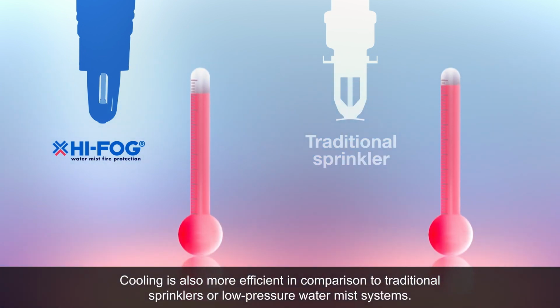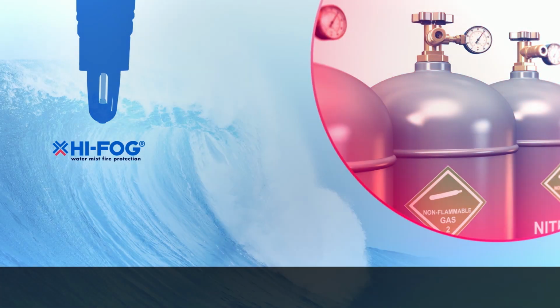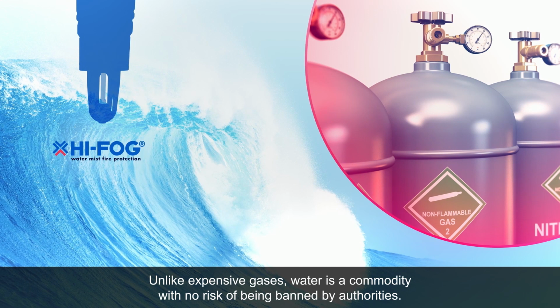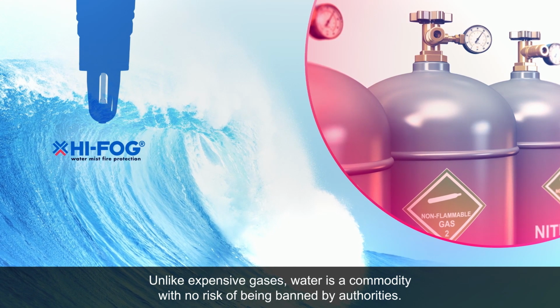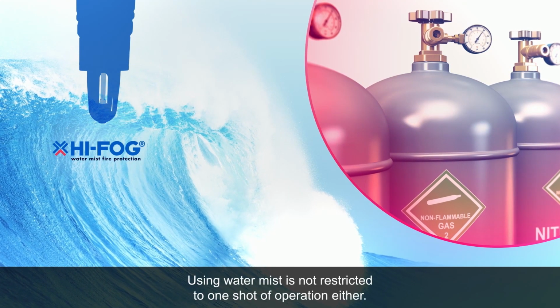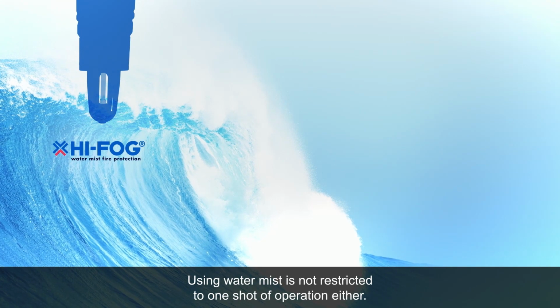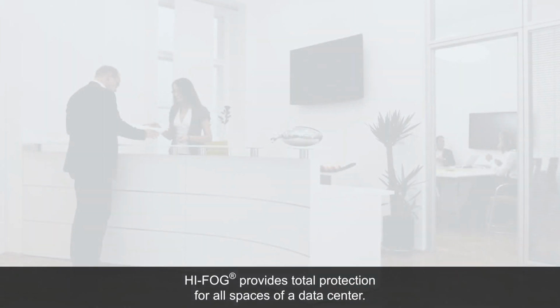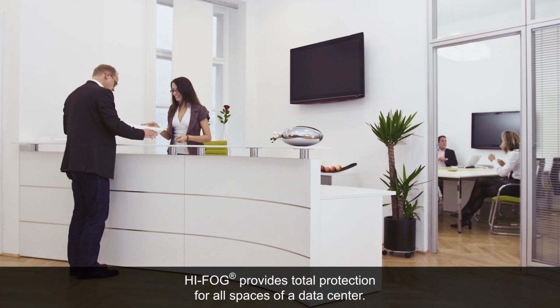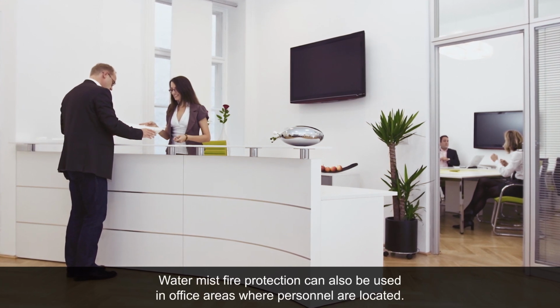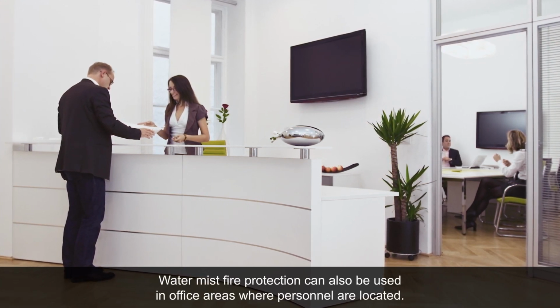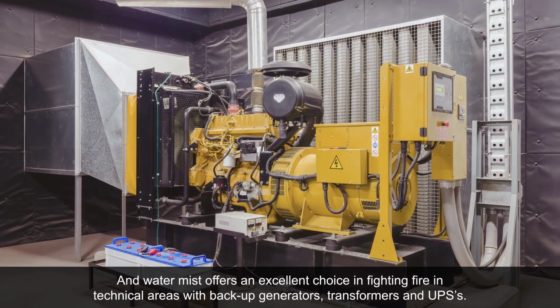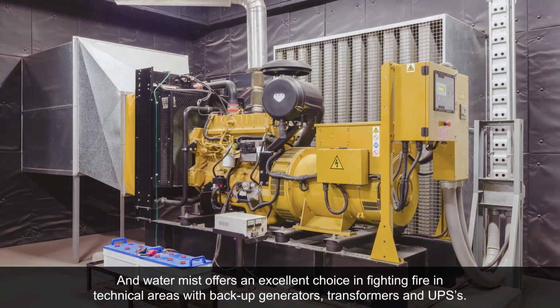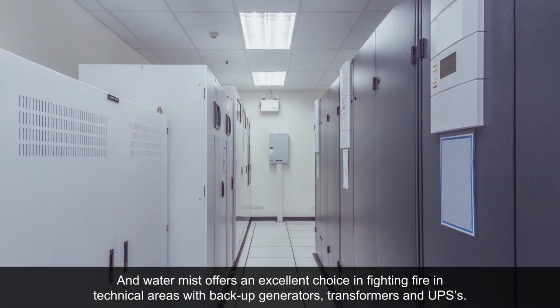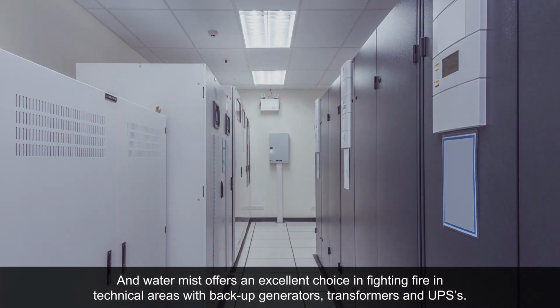Cooling is also more efficient in comparison to traditional sprinklers or low-pressure water mist systems. Unlike expensive gases, water is a commodity with no risk of being banned by authorities. Using water mist is not restricted to one shot of operation either. Hi-Fog provides total protection for all spaces of a data center. Water mist fire protection can also be used in office areas where personnel are located. And water mist offers an excellent choice in fighting fire in technical areas with backup generators, transformers, and UPSs.